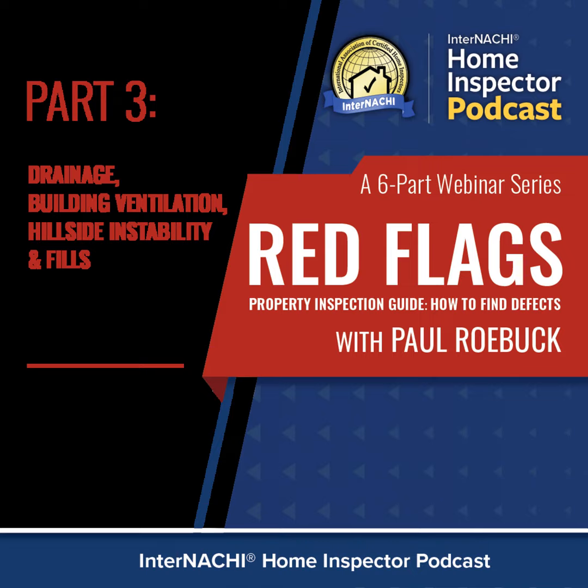So I definitely would write that up as that unit's installed where it makes the area that's supposed to be readily accessible not readily accessible, and it's going to cause an issue down the road. Why they do that, your guess is as good as mine. I call it a bad day. I call it stupidity. I call it just inadequate knowledge of how things should be installed. Somebody just wanting to get a system in no matter what.